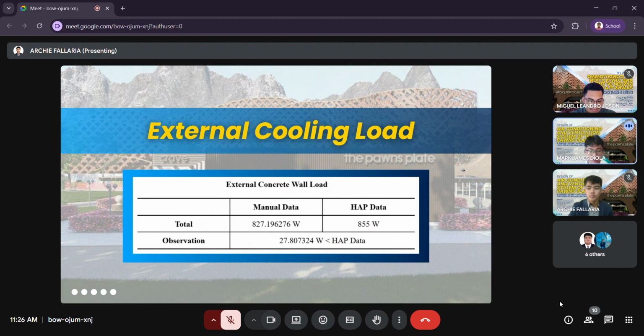So the table presents the total exterior wall load and its comparison with the corresponding HAP, or Hourly Analysis Program, data. Based on the manual computations, the total heat gain from all external walls of the restaurant is approximately 827.20 watts. This value accounts for the solar heat gain and the conduction through the north, south, east, and west facing walls, taking into consideration their orientation, surface area, and material properties, and also the climate's impact during the hottest month. When compared to the HAP software output, which estimated the load at 855 watts, the difference is minimal at 27.81 watts, showing a high level of accuracy in the manual calculations.